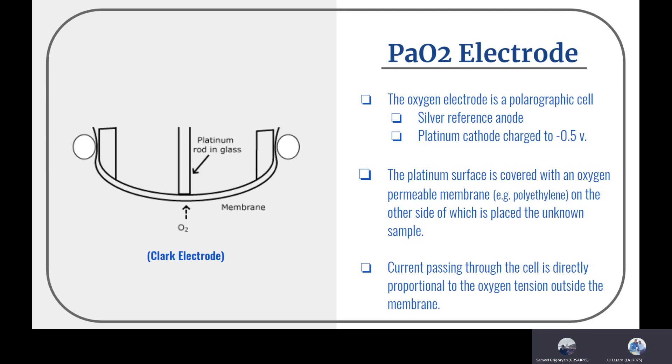The PaO2 electrode is an oxygen electrode, a polarographic cell. The platinum rod inside is covered with an oxygen-permeable membrane known as polyethylene, and on the other side is where the unknown sample is set. Based on how much oxygen goes across the membrane, that's how we calculate the oxygen concentration of the sample.